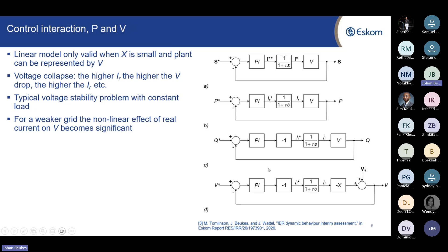If you elaborate further on the interaction between the P and V loop in control systems, you can see the way they interact. You can go into the maths, but the important thing is that the interaction between the P and V loop is a function of X and IR, where X is grid strength and IR is the amount of active power injected into the grid. That is then non-linearly coupled with the P loop again.